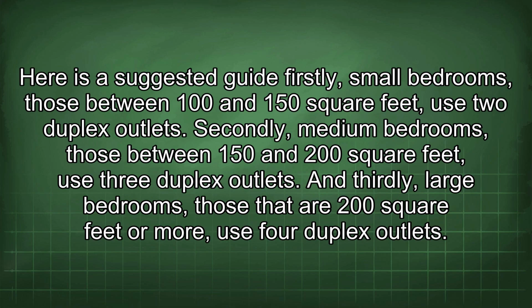Firstly, small bedrooms, those between 100 and 150 square feet, use 2 duplex outlets. Secondly, medium bedrooms, those between 150 and 200 square feet, use 3 duplex outlets. And thirdly, large bedrooms, those that are 200 square feet or more, use 4 duplex outlets.